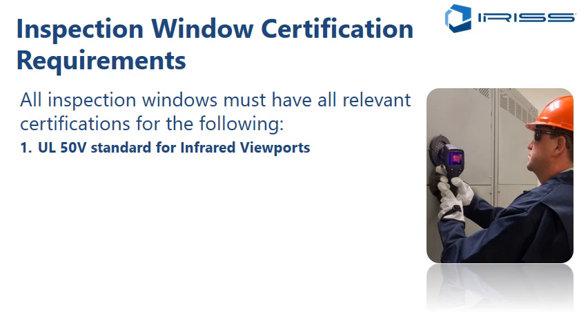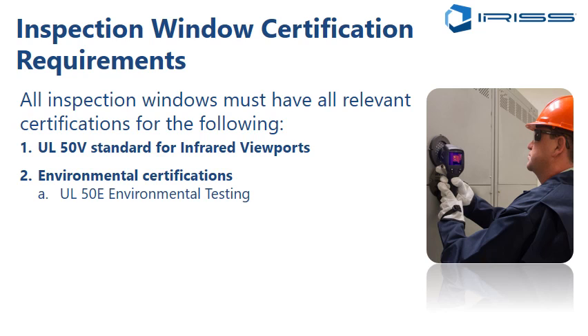So this standard was brought out with the requirements for the mechanical systems involved in an infrared viewport, and in this case we utilize these standards for the mechanical inspection windows anyway. Environmental certifications. This is another area you need to make sure you're covered. So UL 50E is the standard for environmental testing. The IP ratings, the ingress protection ratings need to be maintained.